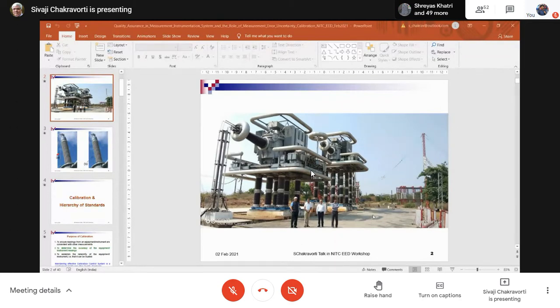Now you can see this is a testing lab in India. And you can see I was standing there. Now on the back side, you can see these two, right? These are two testing transformers. Each transformer can generate up to 500 kV. And together they can go up to, sorry, this is 750 kV. Together they can go up to 1500 kV AC, 50 hertz.